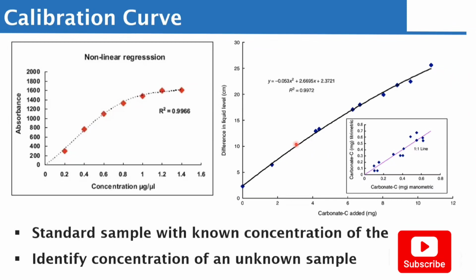So, for example, from 5 to 20, if the result of that patient is very low, abnormally low, less than 5, the analyzer cannot measure it. Because of what? The calibration curve is generated between 5 to 20. Does that make sense? And again, if the sample is abnormally higher than 20, let's say you get something like 20.5, or 21 or 22, because the curve is between 5 to 20, the analyzer cannot measure it. And that means in such a situation, you have to run that test manually. I hope that makes sense.